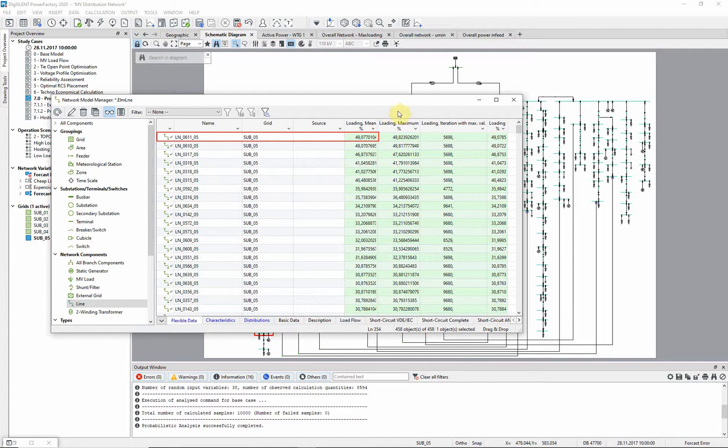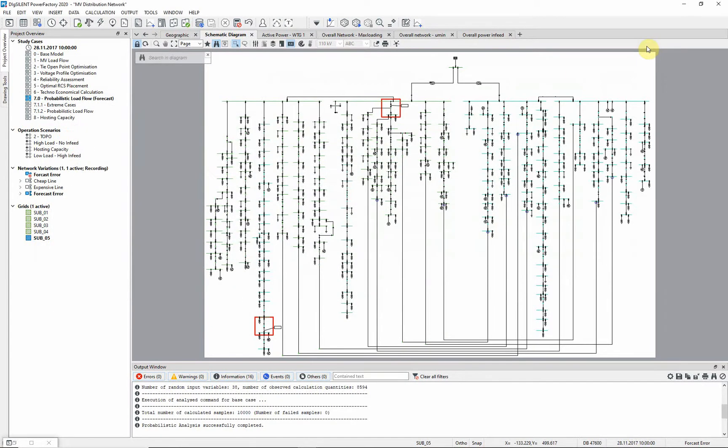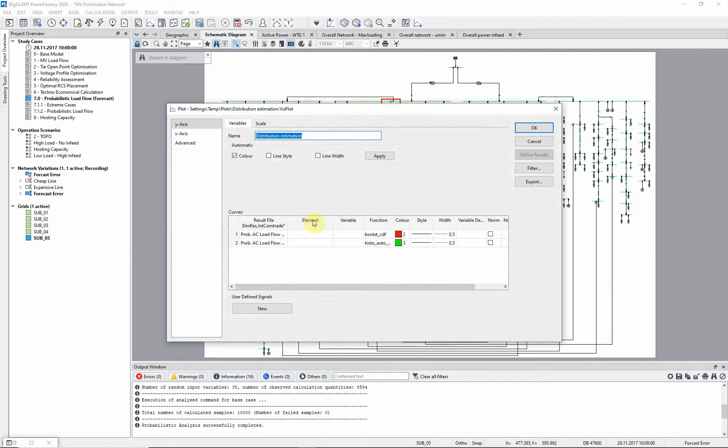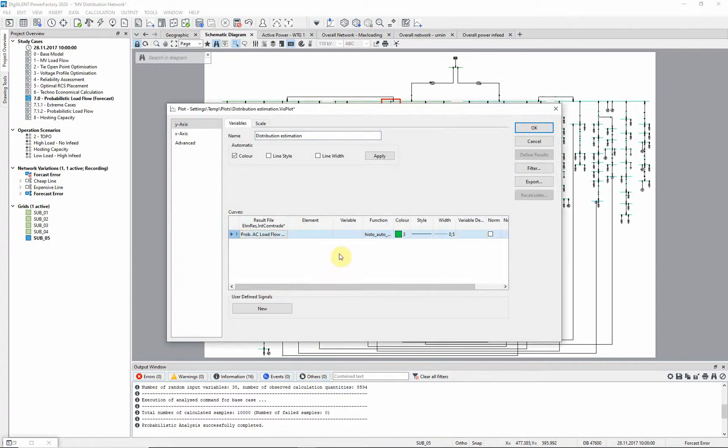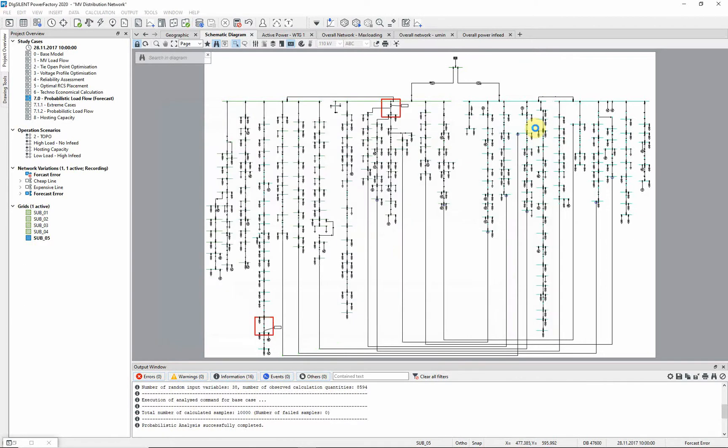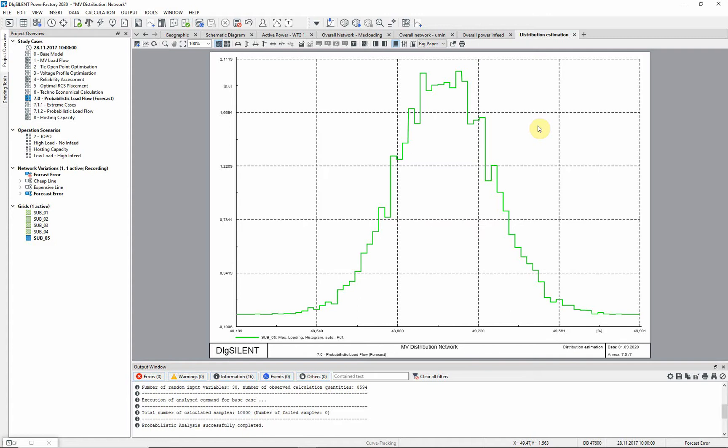Another way to analyze results is by plots. Plots for the probabilistic analysis can be created via the Create Plot icon. Different plot types are available. We will create a distribution estimation plot. In this example, we can delete the first row, since we want to represent the curve as probability density function that is estimated via the histogram method. As element we select the grid sub-05 and max loading as the parameter. The diagram shows us the frequency distribution of the maximum loading in the network. Since only normal distributions have been used in this network, this curve also reflects the shape of this kind of distribution.